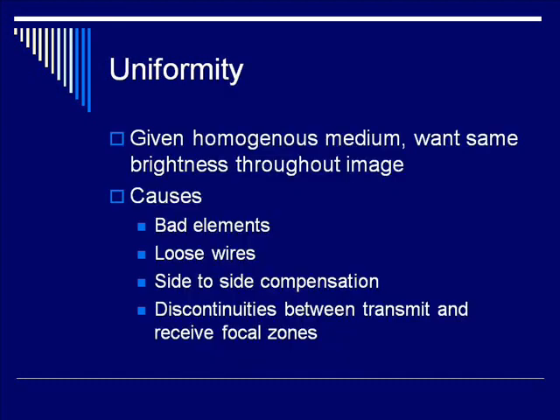One of the properties we would measure using a tissue-mimicking phantom is called uniformity. Uniformity basically means that if you're looking at the same tissue underneath the probe, you want it all to look the same. Liver should look like liver everywhere; kidney should look like kidney everywhere. Liver in the near field should look like liver in the far field. More rigorously, given a homogenous medium, we want to have the same brightness throughout the image.